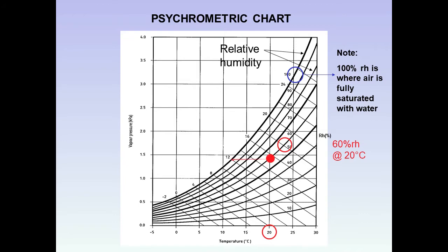We then extend from that mark horizontally to the 100% line — that is where the air is fully saturated with water and can no longer retain the water present. We then drop a vertical line down to the base. This tells us that the air is saturated at 12 degrees.